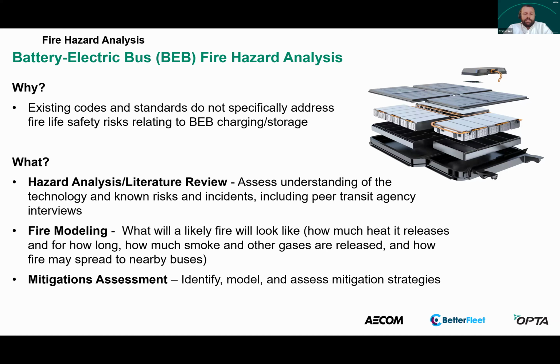So with that being said, I do recommend referring to documents like NFPA 551, which is the guide for the evaluation of fire risk assessments, as well as the Society of Fire Protection Engineers guide for risk assessments, when developing and reviewing FHAs, as well as the most current codes and standards, and then outlining the requirements for battery systems. NFPA 855, which is the standard for the installation of stationary energy storage systems, as well as the International Fire Code here in the States, are updating the requirements based on all the new research available.